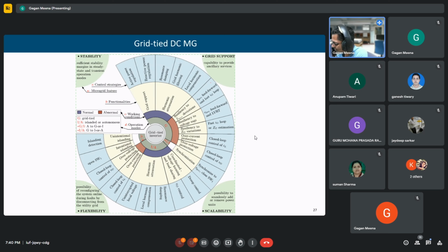So in December 2022, there was a blackout in Mumbai. One generator was not available. It was taken out due to maintenance. It was to be synchronized again, about to be brought on bar after a few slots, and that happened after a few hours, and the blackout happened before that. Several studies were done here at IIT Bombay also. It was found that if such energy storage or such a microgrid had been there, then that could have been avoided.